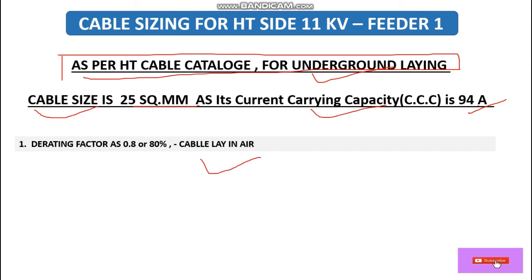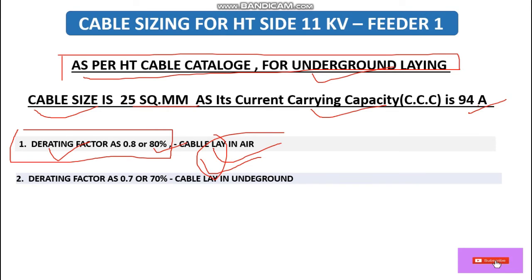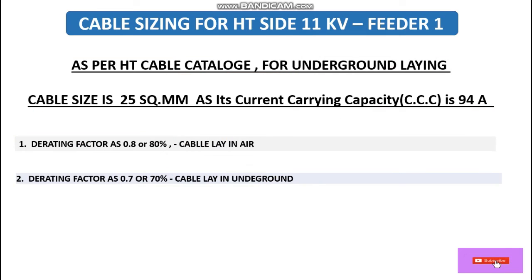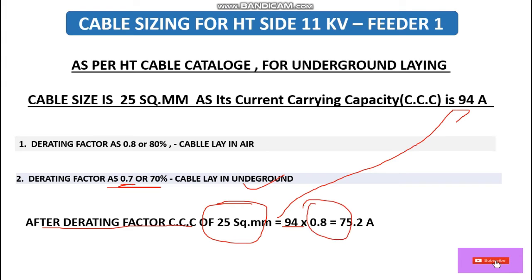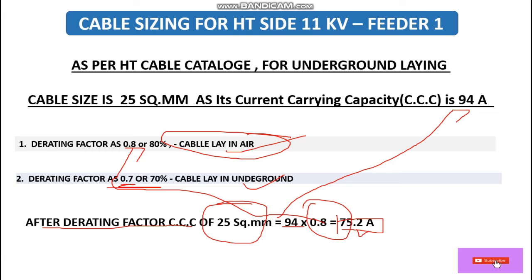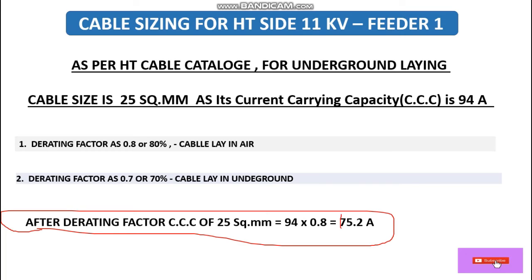When laying the cable in air, we must also consider a derating factor for safety. If laid in air, the derating factor is 0.8 (80%). If laid underground, the derating factor is 0.7 (70%). Since we are laying in air here, we apply 0.8. After applying the derating factor: 94 × 0.8 = 75.2 amperes.